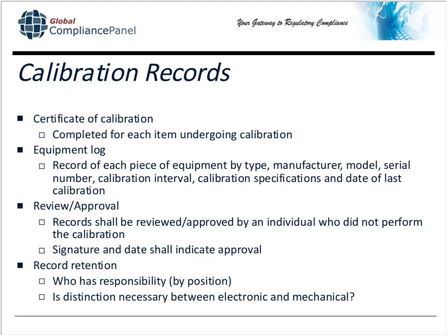Something you've got to determine also is record retention. Who keeps these records? I recommend that in your procedure you reference by position. Most of us have a calibration tech, so that's pretty much a no-brainer. And if you distinguish, as I mentioned on an earlier slide, between electronic pieces of equipment and mechanical pieces of equipment, some firms choose to separate these. For example, they may have production engineering or manufacturing engineering maintain the calibration records for electronic things, but have quality engineering maintain them for mechanical. Most firms don't do this, but I know firms that do, so I definitely want to include this as part of this presentation.